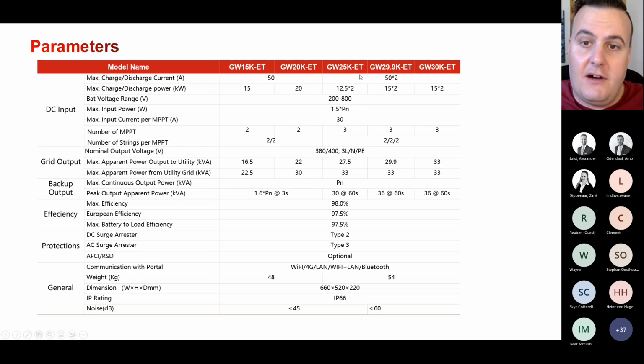As you see, the batteries are high voltage batteries. They go up to 50 amps on an input. The discharge power is as per inverter rating. As you'll see, the larger ones have it split per input, and there's a wide battery voltage range of 200 to 800 volts.